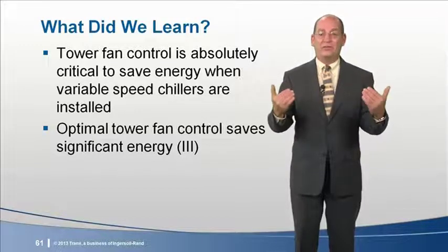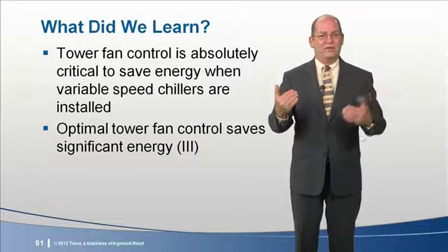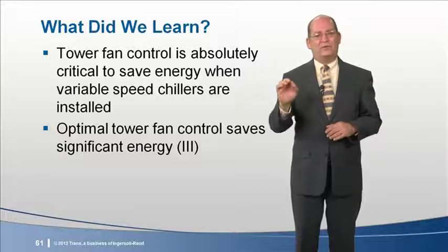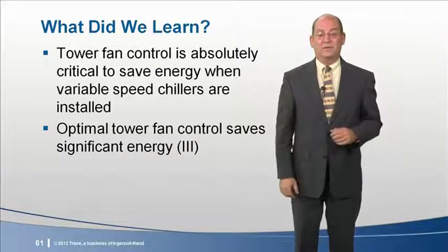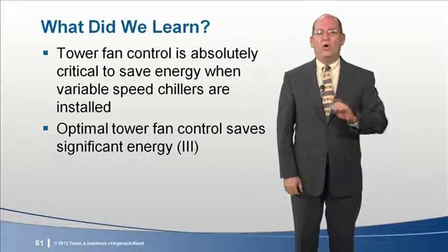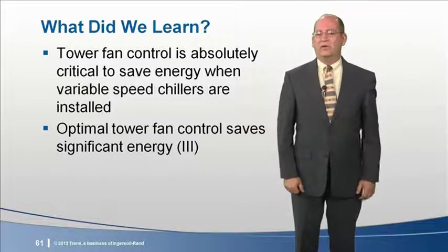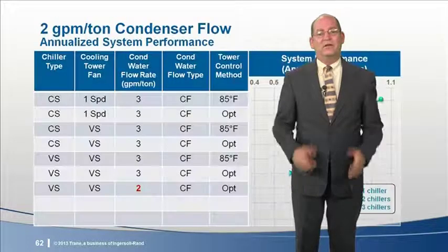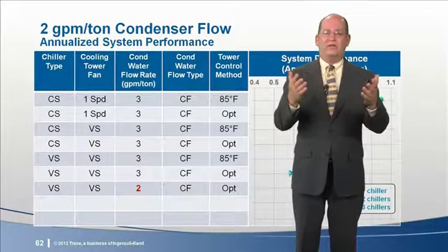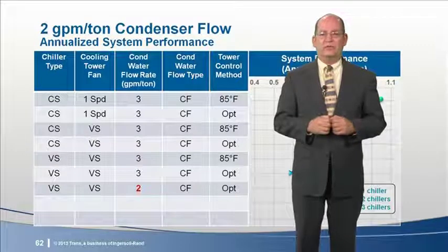Now this is the 3rd time we've reached that conclusion. Perhaps it's time for optimal tower set point control to become another fan law. From here on, all our alternatives are going to use optimized cooling tower fan control. Next, let's look at changing the design condenser water flow rate.